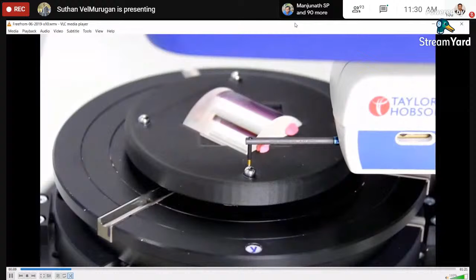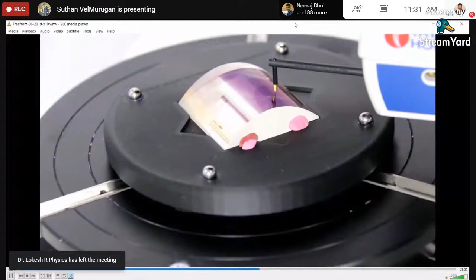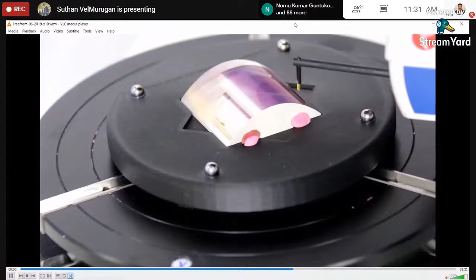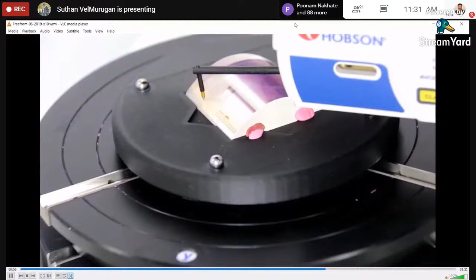So why is it measuring the ball? It is to locate the position of the fixture. That is my reference. The balls are in a fixed position. From there, it will find out where exactly I am placing the part in the middle. So it is multiple 2D traces at a certain distance, and the distance can be defined before measurement. You can define in microns, every 10 microns, or every 1 millimeter, or every 5 millimeters. Accordingly, it will move, measure, and then generate a 3D surface of it. So it has covered the entire portion of the surface.